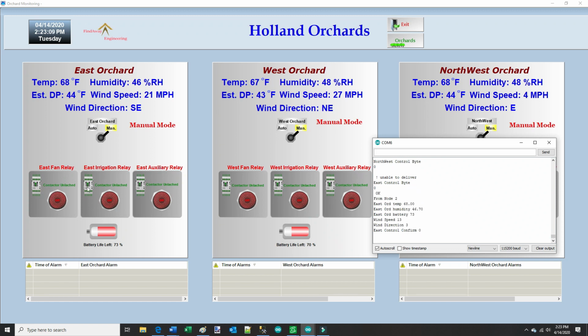I have icons that are telling me what state those contactors are in the field. These are signals coming off the auxiliary contacts on those contactors. So right now you can see everything's unlatched. And the way I'm transmitting these control commands is bits in a byte. So I have 1, 2, and 4. If all 3 of these are on, the number in the byte sent is 7. If this is on, it's 1. If this is only on, it's 2. So if 2 and this are on, it's 6. And if this and this are on, it's 3.